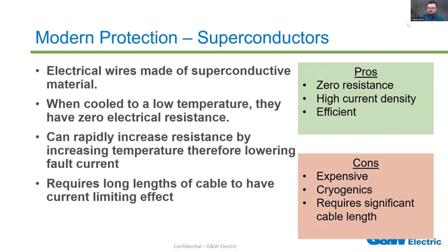Another new technology to keep an eye out for is superconductors. You're typically going to see these more in the high voltage transmission world, specifically in long distance DC transmission lines. These are electrical wires made of superconducting materials. Generally, when they're cooled to a low temperature, they have near zero electrical resistance. You can use this as a current limiting device by rapidly increasing that resistance by increasing temperature. That would therefore lower the available fault current by, once again, increasing resistance. However, it's important to note that in order to have this current limiting effect, in order to add enough resistance or impedance to your system, you do need a very long length of cable. Think in the realm of kilometers or miles.